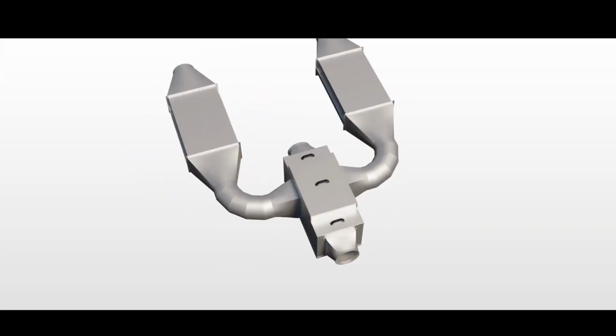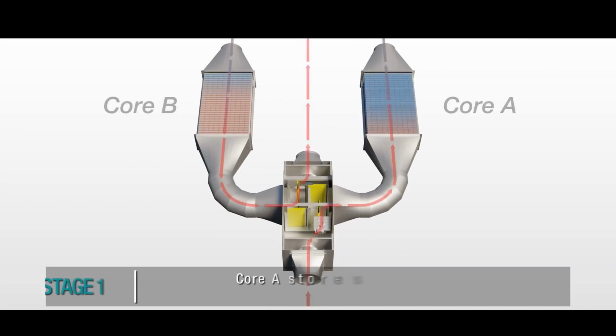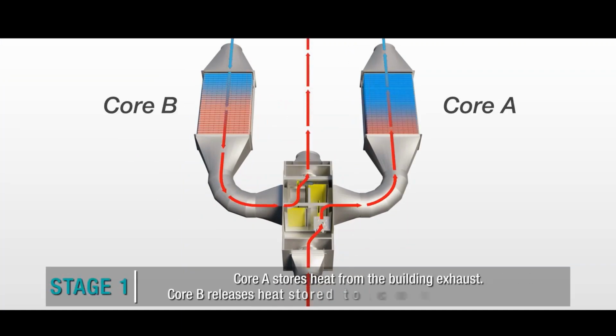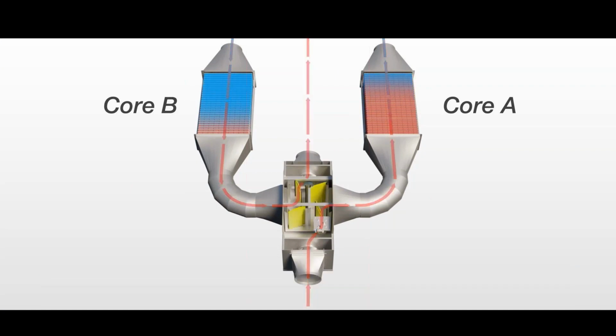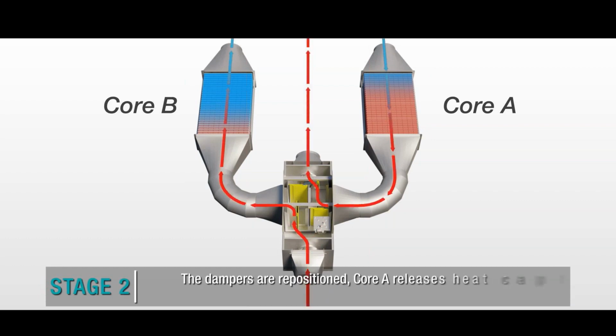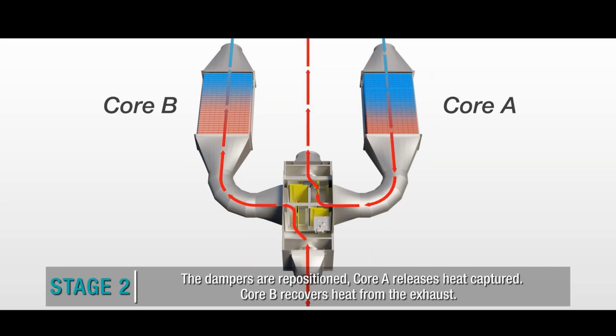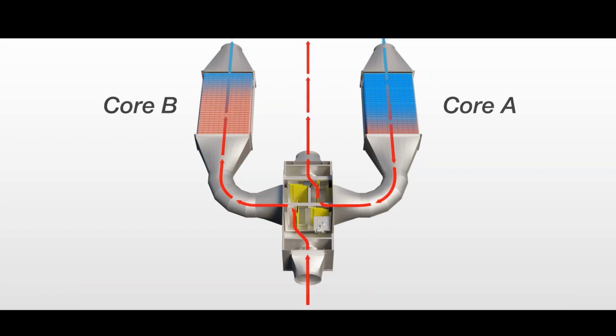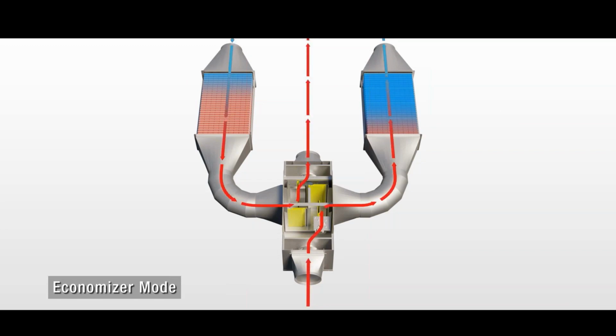The RegenCore Flex features a 2-stage energy recovery process. During the first stage, Core A stores heat from the building exhaust, while Core B releases heat previously stored to condition the cold outdoor supply air. In stage 2, the dampers are repositioned, allowing Core A to release the heated air captured and stored during stage 1, while Core B recovers heat from the exhaust. The 4-damper design also enables economizer mode, which uses outdoor air for cooling, leading to additional savings.